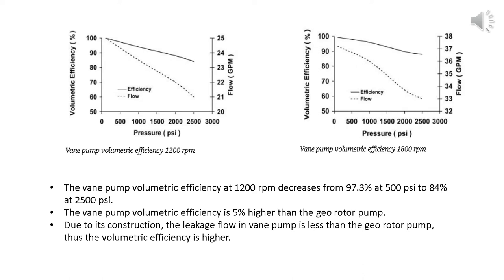According to my analysis, the vane pump volumetric efficiency at 1200 RPM decreases from 97.3% at 500 PSI to 84% at 2500 PSI. The vane pump volumetric efficiency is 5% higher than the georotor pump. Due to its construction, the leakage flow in vane pump is less than the georotor pump, thus the volumetric efficiency is higher.